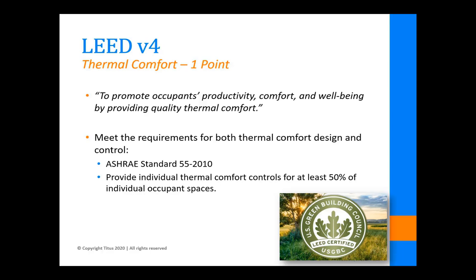For buildings being designed to the LEED 4 standard, the thermal comfort point can be obtained by meeting ASHRAE standard 55, which specifies conditions for acceptable thermal comfort. The building must also be designed so that individual thermal comfort controls are provided for at least 50% of individual occupant spaces. This single thermal comfort LEED point will be quite costly to obtain with a conventional VAV system, as every other room would have to be fitted with a VAV box and DDC controls.